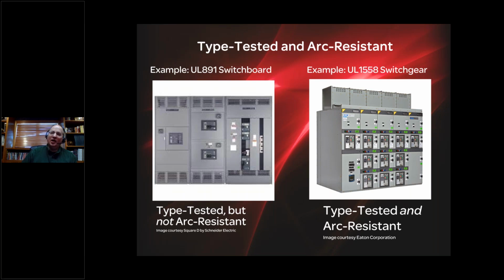The vents in this case are on those plenums at the top of the gear, which are typically extended to exhaust plenums out the roof or side of a building where the exhaust plasma cannot harm anybody. But I want to be clear. In the event of an arc flash event in either of these pieces of equipment, the one on the left or the one on the right, the equipment itself, if it's mechanically vented like the one on the right, can and frequently is catastrophically damaged beyond the ability for practical or economic field repair.